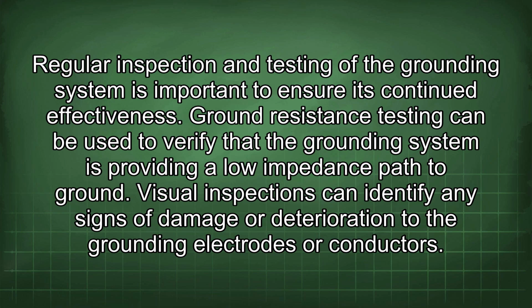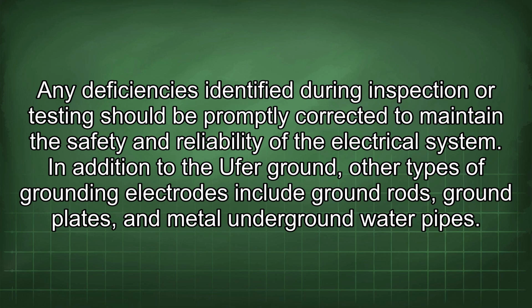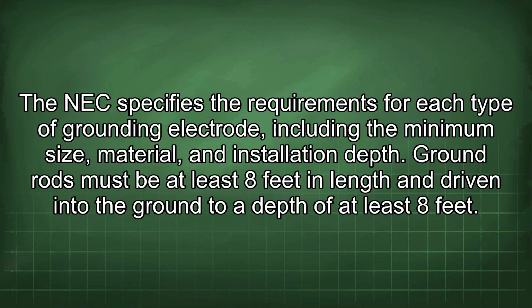Ground resistance testing can be used to verify that the grounding system is providing a low impedance path to ground. Visual inspections can identify any signs of damage or deterioration to the grounding electrodes or conductors. Any deficiencies identified during inspection or testing should be promptly corrected to maintain the safety and reliability of the electrical system. In addition to the Ufer ground, other types of grounding electrodes include ground rods, ground plates, and metal underground water pipes.